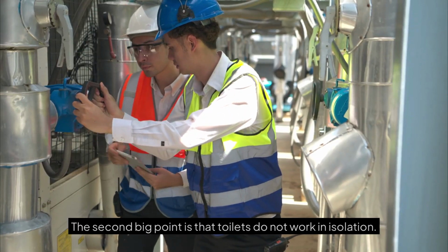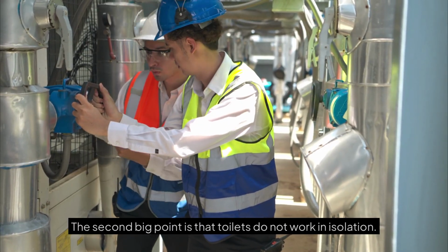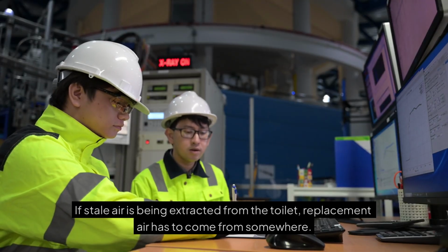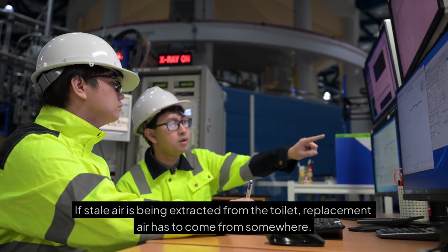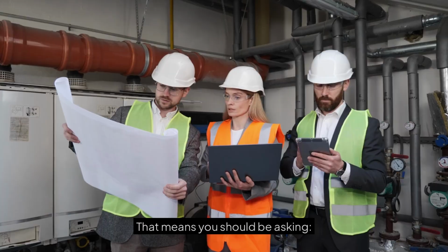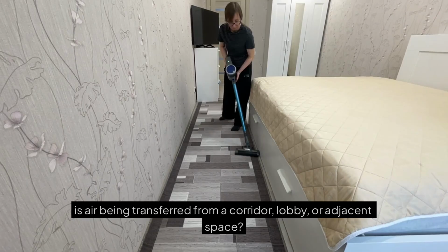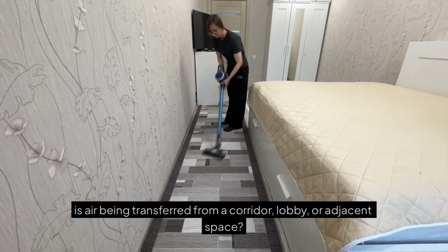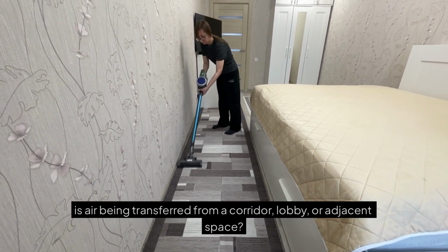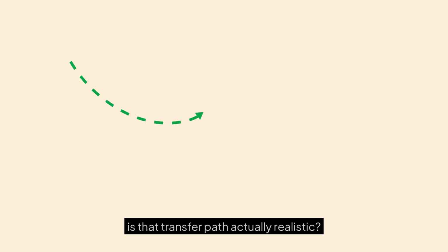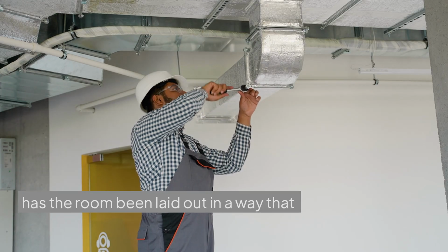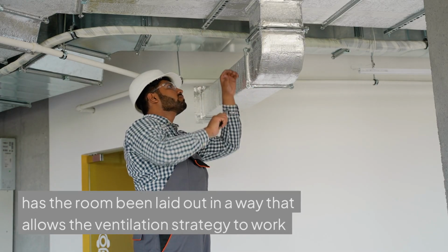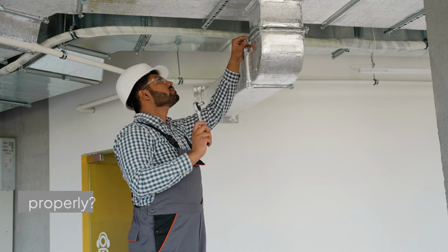The second big point is that toilets do not work in isolation. If stale air is being extracted from the toilet, replacement air has to come from somewhere. That means you should be asking, is air being transferred from a corridor, lobby, or adjacent space? Is that transfer path actually realistic? Has the room been laid out in a way that allows the ventilation strategy to work properly?